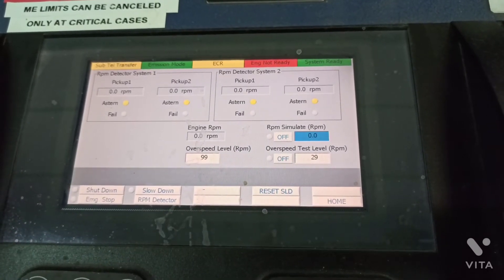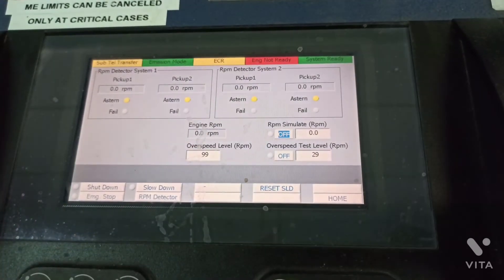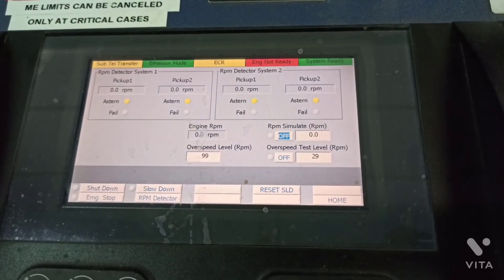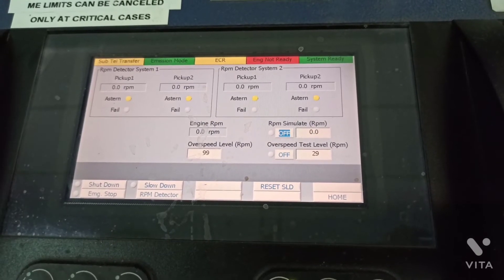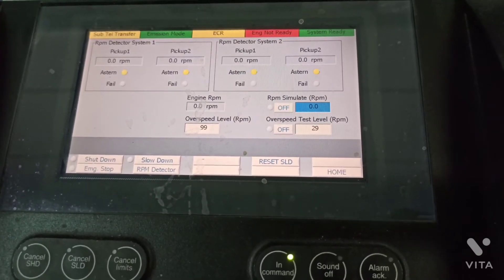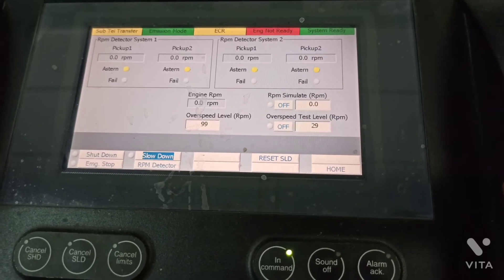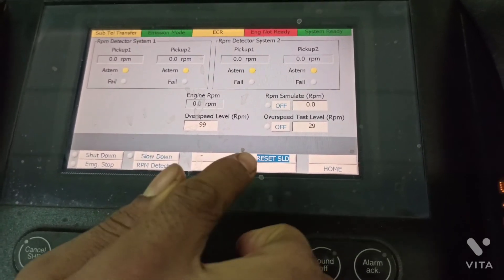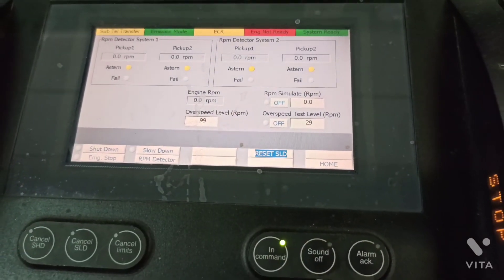Once that's done, you need to turn on RPM simulation, then increase the RPM on RPM simulation. Once it's completed, you need to turn off RPM simulation and over speed test, and the test is completed.